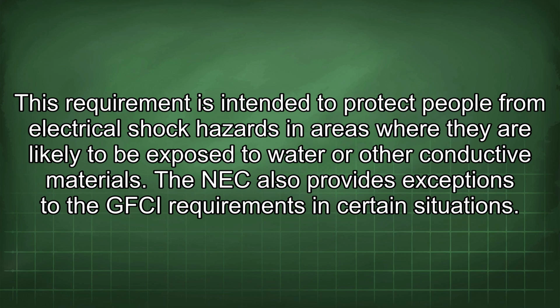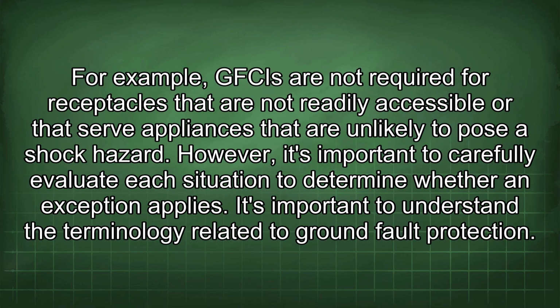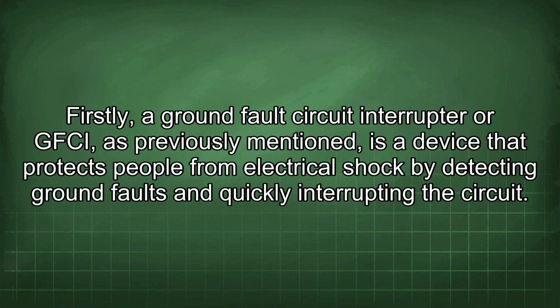The NEC also provides exceptions to the GFCI requirements in certain situations. For example, GFCIs are not required for receptacles that are not readily accessible or that serve appliances that are unlikely to pose a shock hazard. However, it's important to carefully evaluate each situation to determine whether an exception applies. It's important to understand the terminology related to ground fault protection. Firstly, a ground fault circuit interrupter, or GFCI, as previously mentioned, is a device that protects people from electrical shock by detecting ground faults and quickly interrupting the circuit.